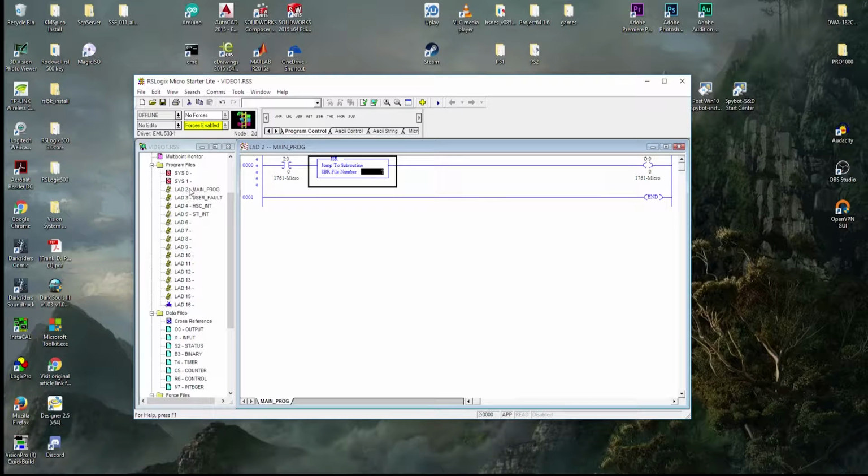a whole bunch of different ladders in this case. So you have your program, and you have HSC, which is a high-speed counter, which is for encoders. Like an encoder is something that you put onto a conveyor belt so that you know exactly what position the product is on top of it. So let's say you have boxes going down a conveyor and you put an encoder on it, and the encoder updates every 1/10 of an inch. And so you know every 1/10 of an inch where that box will be. So you can do timers and stuff like that off of it, or you can just say, oh, in 5 inches, I want this box to take a picture, or a camera to take a picture on this box, and then 3 inches after that, I want to blow it off if it's bad, or something like that.